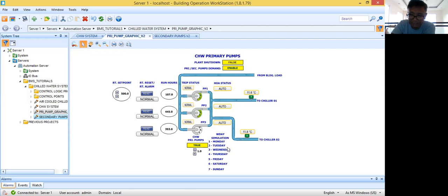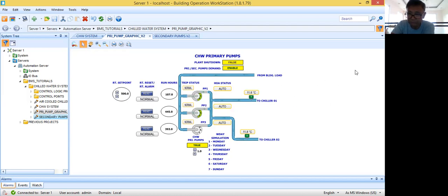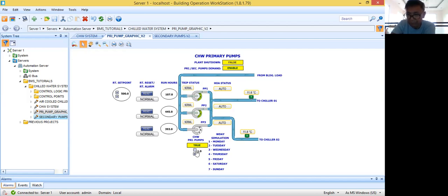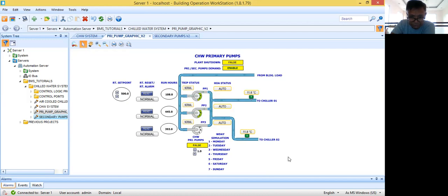In my control logic program, I tried to sequence the pumps on a daily basis. Every day there will be two pumps running. So every Monday, there will be a set of pumps serving the chilled water requirement of the building. I have here a weekday simulation toggle — if this is set to true, I will follow the simulation; if I put it to false, it will follow the actual day in my system. Today is Monday, so pump one and pump two are running.